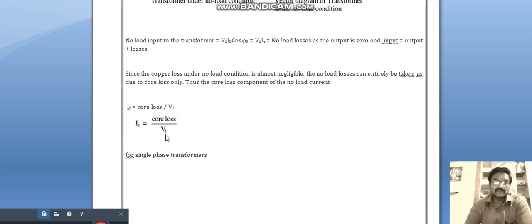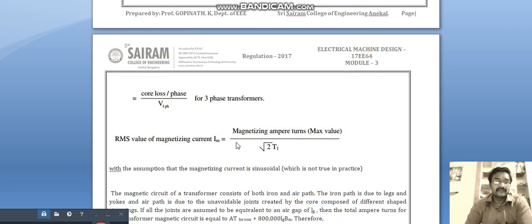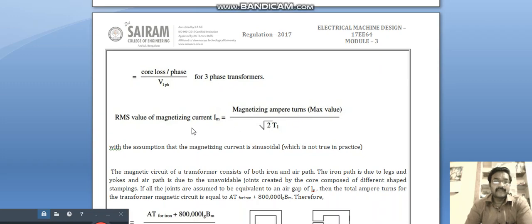Ic is equal to core loss by V1 for single phase transformer, or core loss per phase by V1 phase for three phase transformer. The RMS value of magnetizing current Im is equal to magnetizing ampere turns max value by square root of two multiplied with T1.